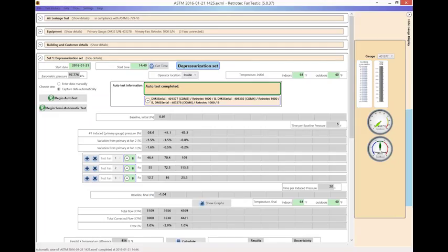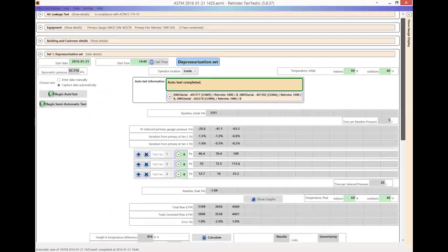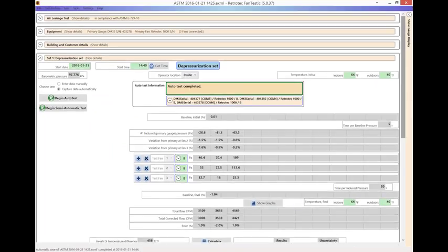Obviously, when you were talking about gauge control, that's only appropriate when you're running more than one fan, which you are, of course. But from testing from high pressure to low pressure, there are a few important things you need to know about that. In the defaults, we put our recommended test pressures and test pressure sequence in there for each standard to give you the maximum chance of passing a test. And the reasons why we go from high to low are many. One is it will achieve 60 pascals faster than it would achieve 10 pascals, so it's faster.